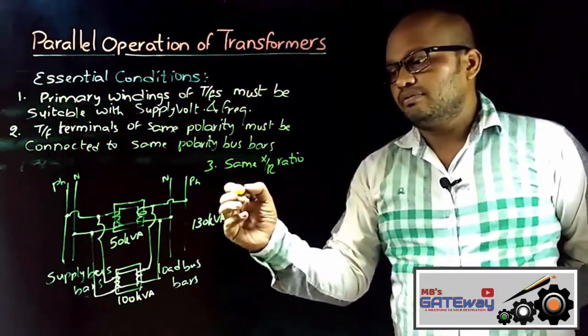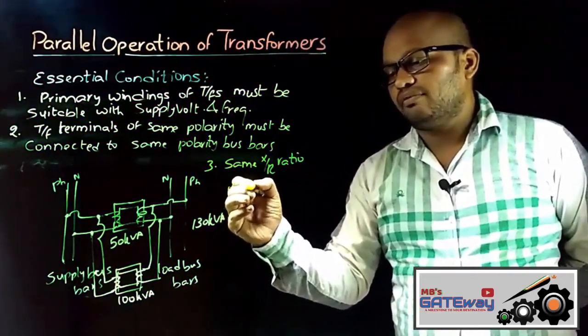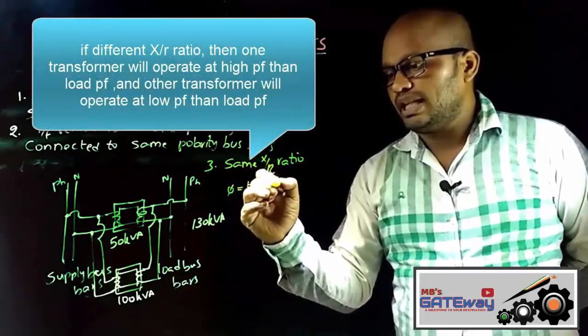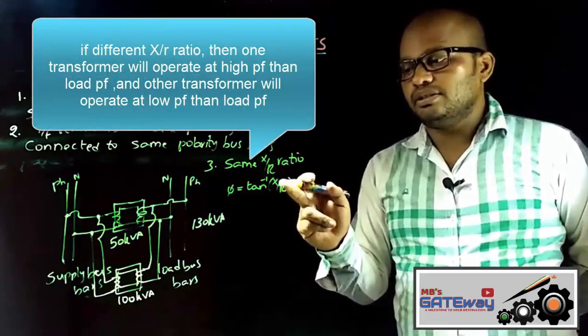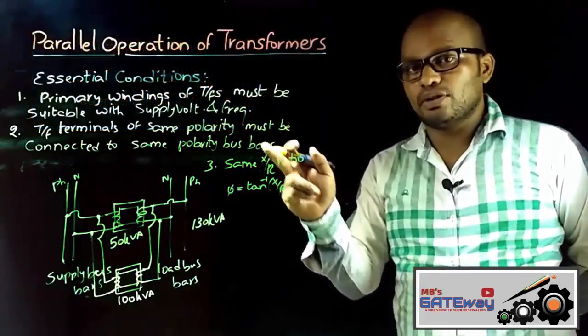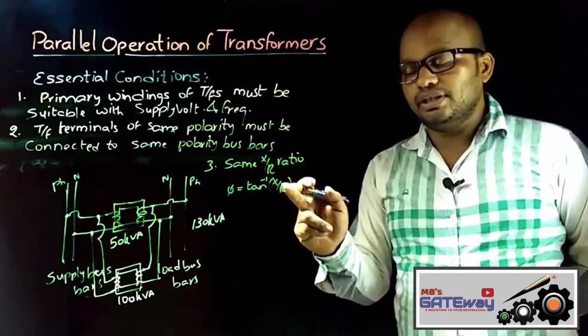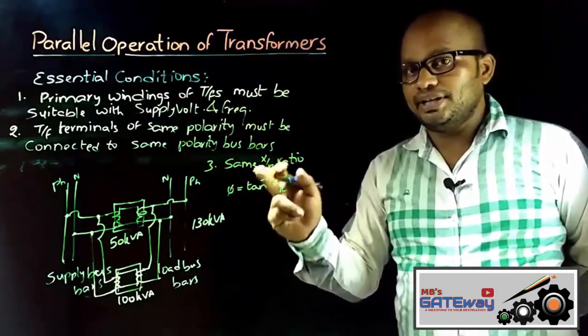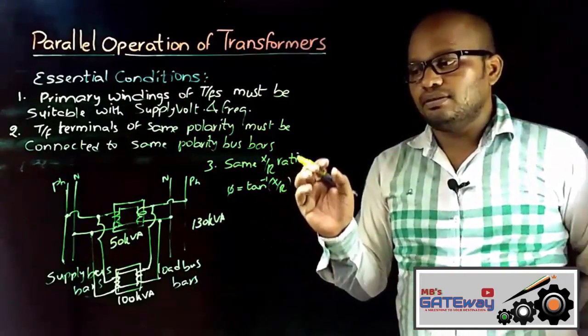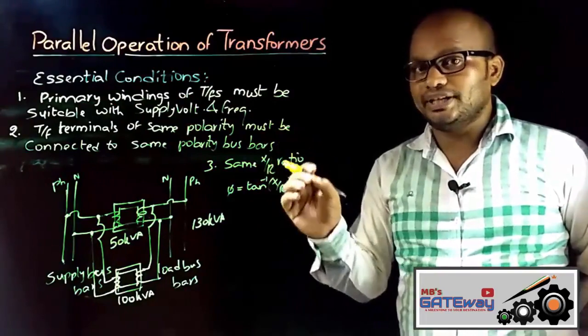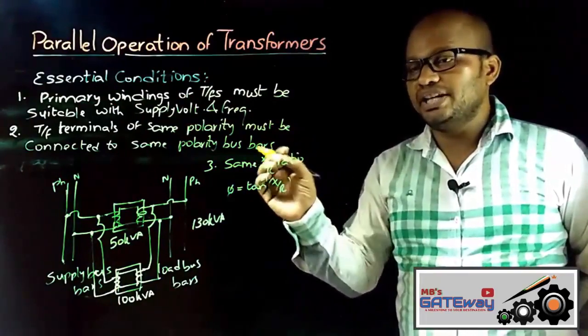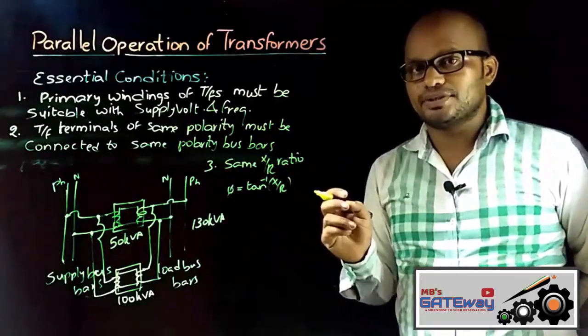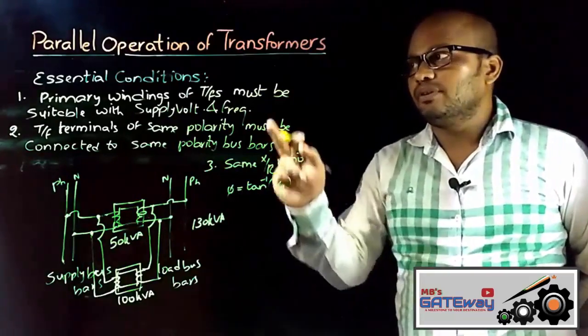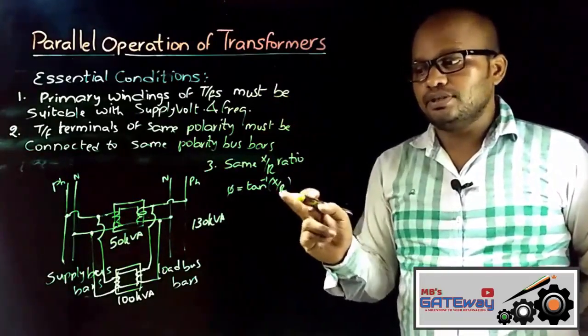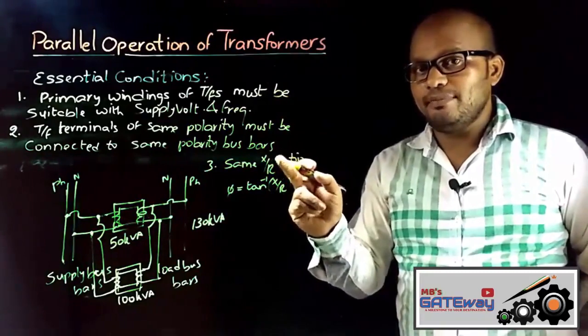We know that the power factor angle phi is equal to tan inverse of X/R, which implies that if transformers have different X/R ratios, then the transformers will operate at different power factors. If the transformers are operating at different power factors, that will lead to unequal load sharing by the transformers. Therefore, for proper parallel operation of transformers, the transformers must have the same X/R ratio.